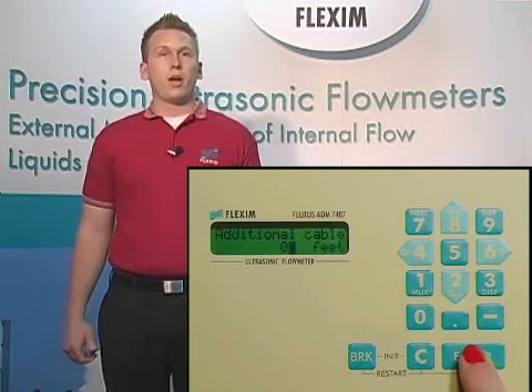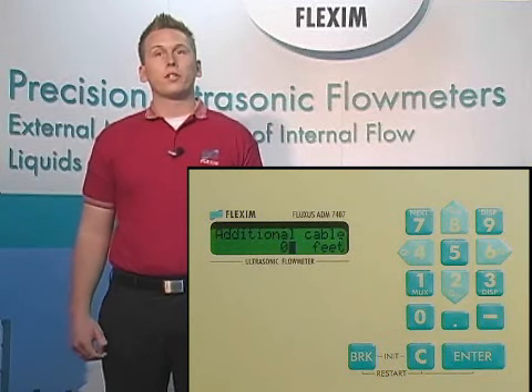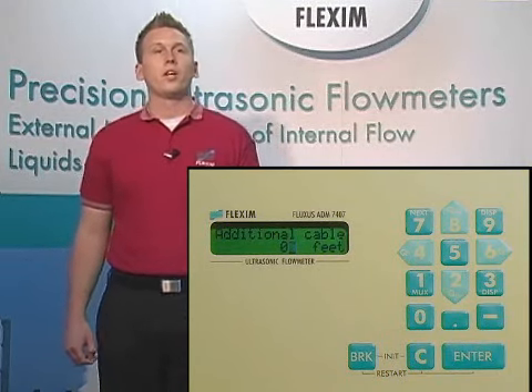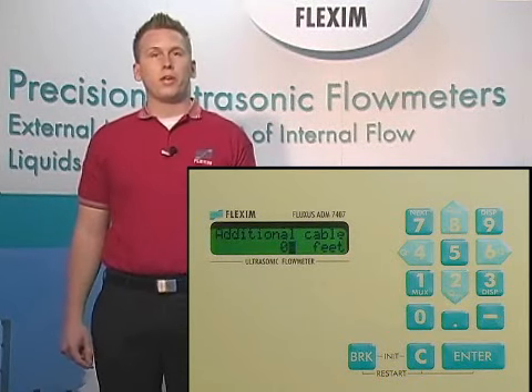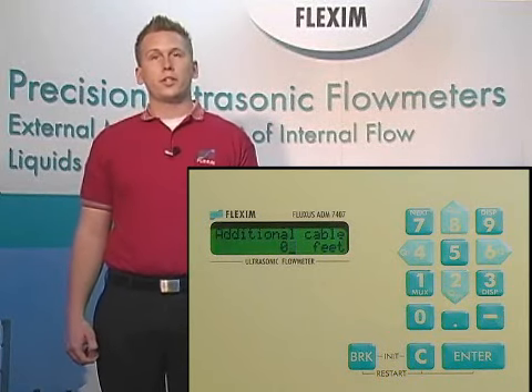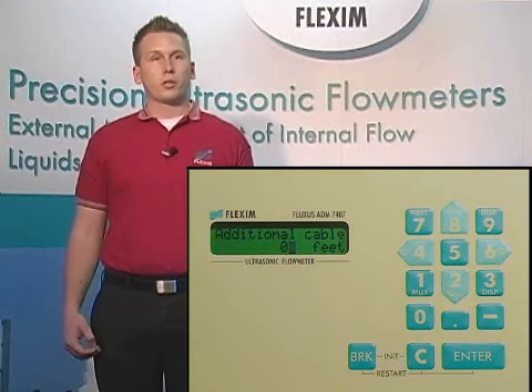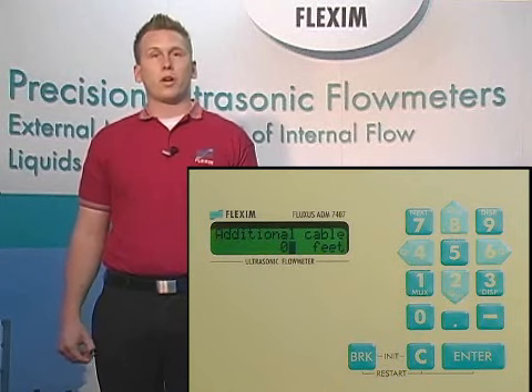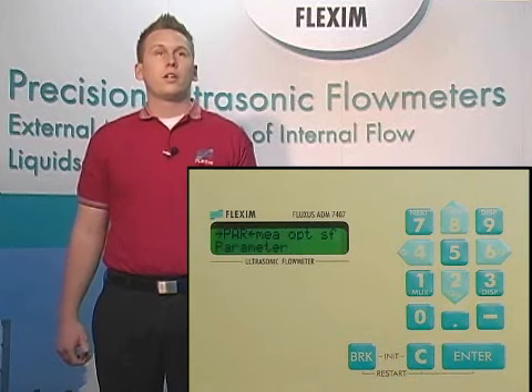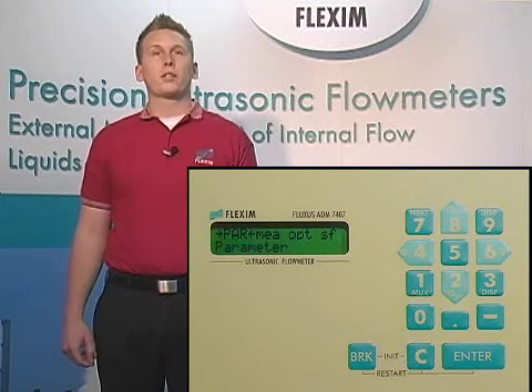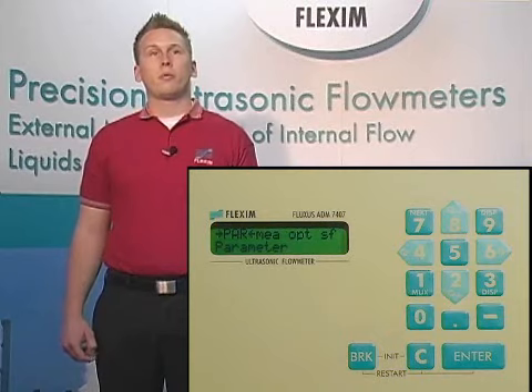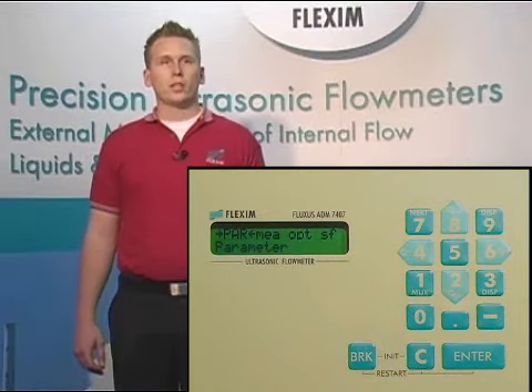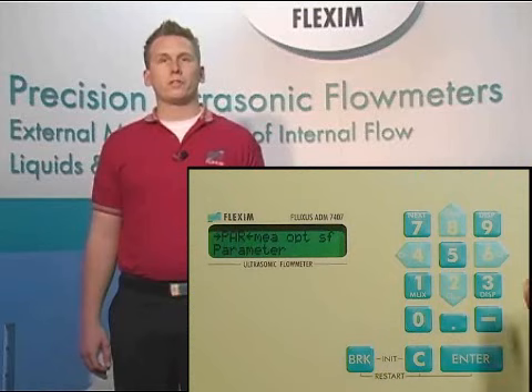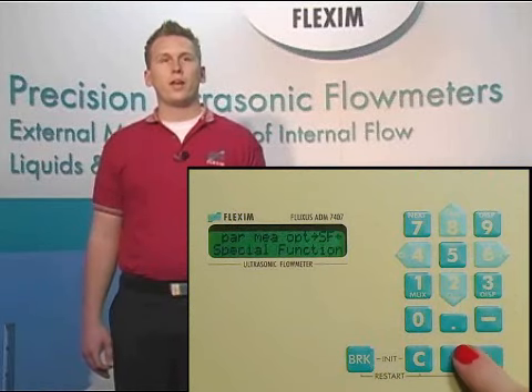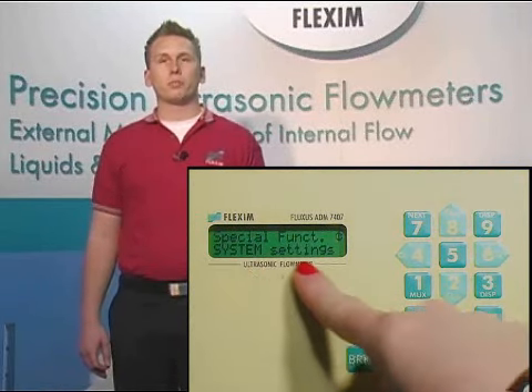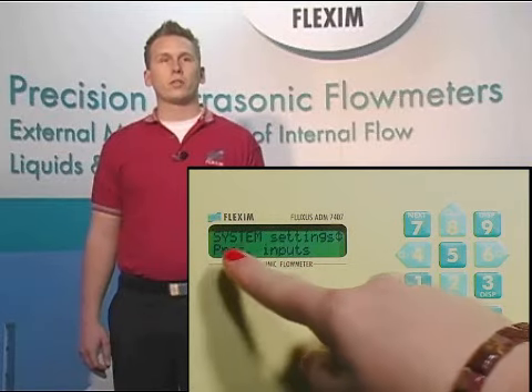The last option under the parameters section we need to enter is the amount of transducer extension cable we're using. If our transducers are connected directly to the meter without any extra cable, we enter 0. If we have used the junction box, we put in the length of cable from the junction box and hit enter. Hitting enter this last time has brought you back to the main menu. And now we're ready to tell the meter about any inputs we like to use. The process inputs section of special functions is found by first going to the special functions menu and hitting enter, then scrolling down until we see process inputs. Hit enter to go into the process inputs.